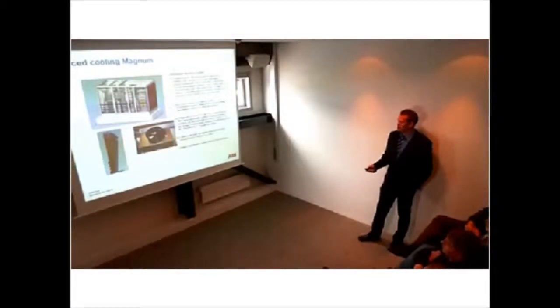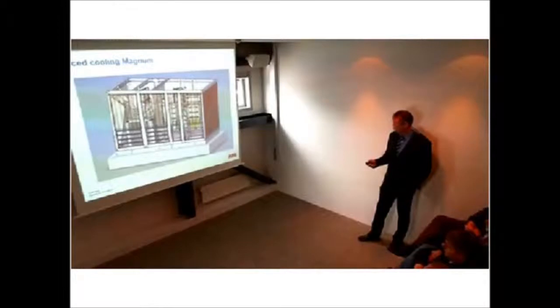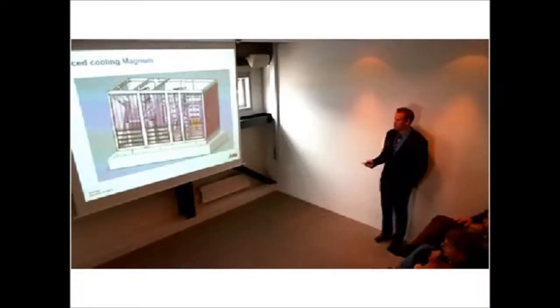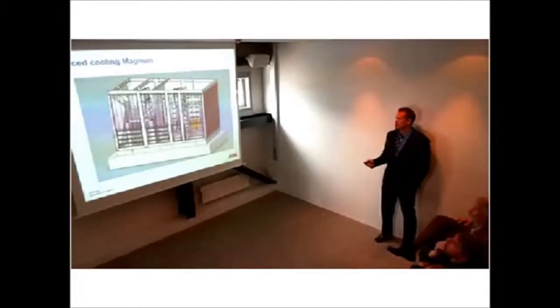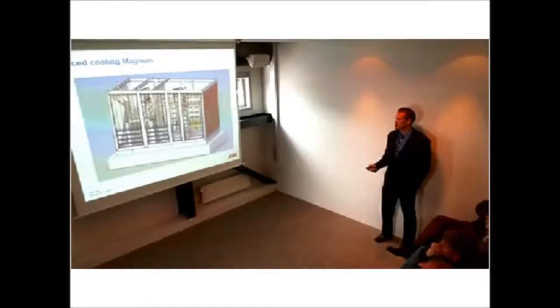If you can see here, this is a wall element you can put next to the transformer. This is a wall element you can put in later. All you need to buy is this wall element, this fan, and this control unit. We have delivered a lot of these in Norway. As you can see, it's at a little bit of an angle, so it usually fits all the substations as well. You can have either 1 or 2 in both wall elements on the back, and this is of course locked from inside the substation. The heat will rise up, and the fan will force it down and out through these ventilation gaps.